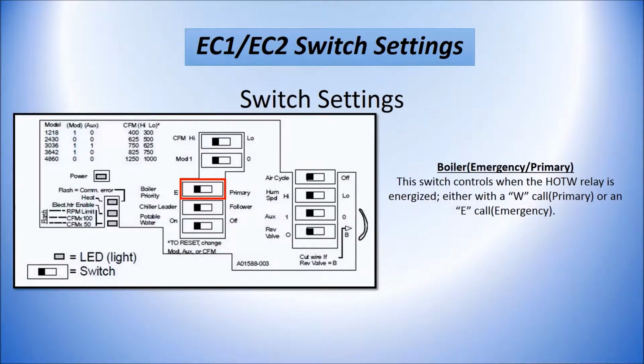The next setting is for the boiler relay. The hot W relay is either going to be energized when it has a W call or an E call from your thermostat. Set the switch for E for emergency, and put it on primary if you want it for a W call. If you have a normal W or W2 call, that's when your hot W relay is going to be energized.